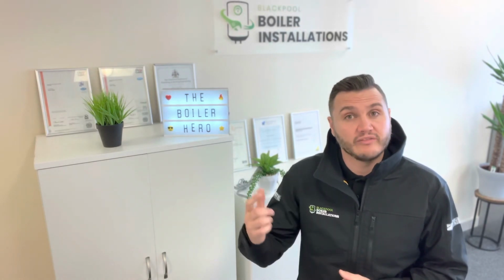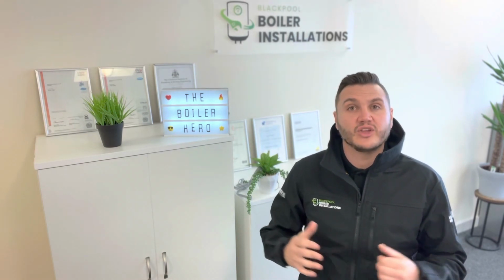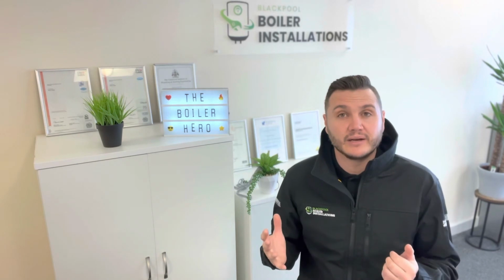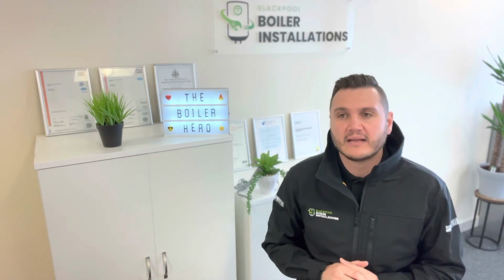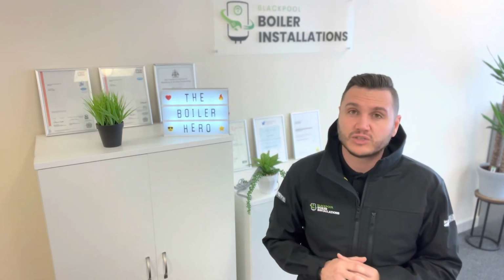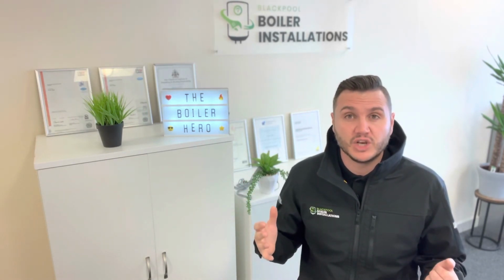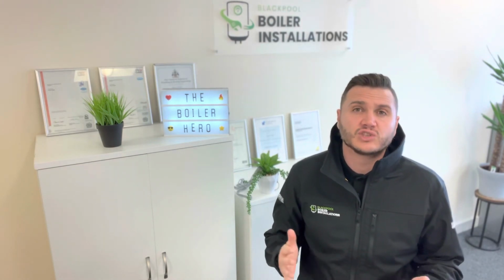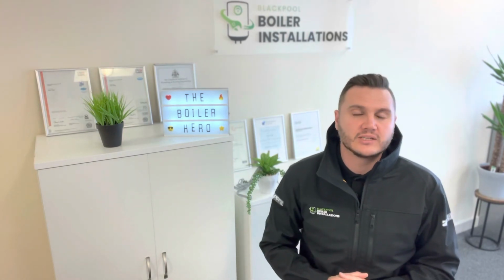And sometimes, again with the pressure thing, you can lose pressure on your boiler, you fill it up, a week, 2 weeks, a month later, the pressure goes down and you have to fill it up again. And we have to wonder why that is. You could have a leak somewhere that you don't know about, or it's all of a sudden happened because you've converted the system so it now can't deal with the new pressure. Unfortunately, if that's the case, we can't just ignore the problem and keep filling the boiler up every week, every month, because we're just going to do more damage to the new boiler. So we'll need to do a trace and repair, so either find the leak or cut the leak out and repipe the system.